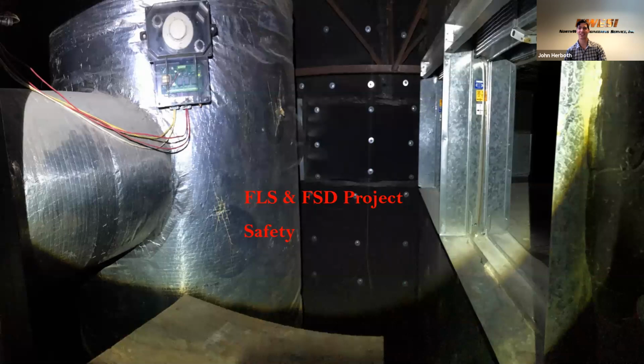One of the last things I come to is safety is going to be a problem. This is an open shaft here with a little metal platform, and somebody gets to go test this stuff. You can be harnessed, sure, but in some situations, how are you going to recover that person? It's improbable that you're going to spend the time for two sets of dampers to come and use this platform. In this situation, we had them cut new access hatches on the right so that we wouldn't have to enter the shaft to facilitate testing these dampers.